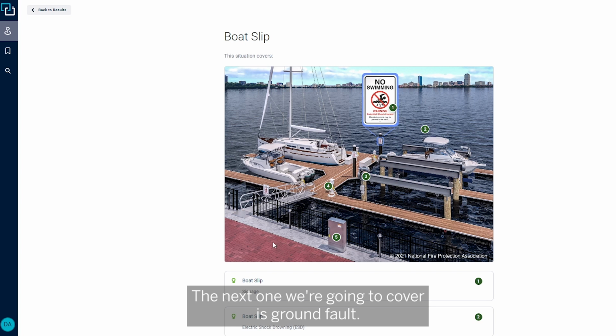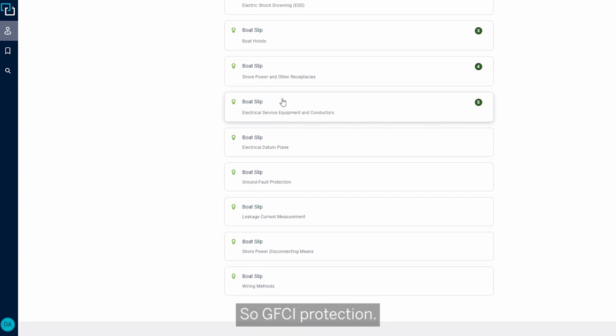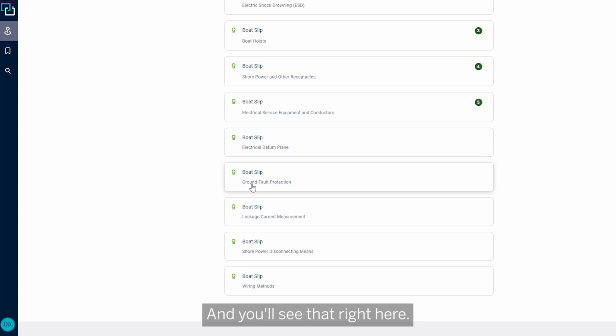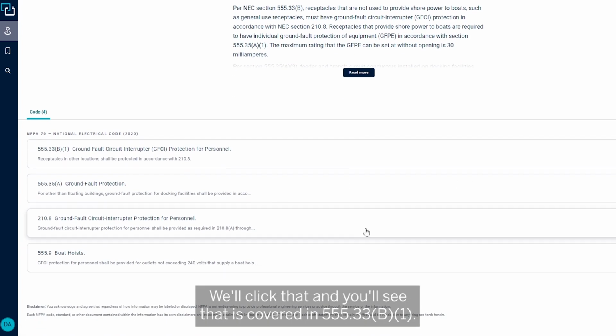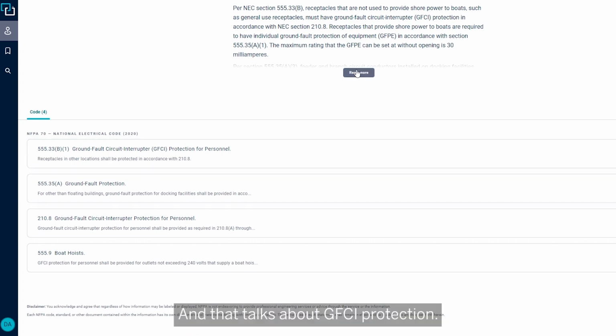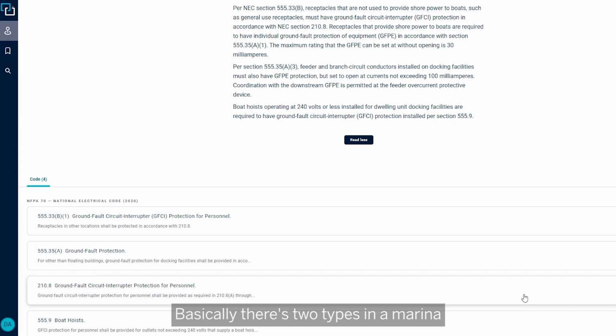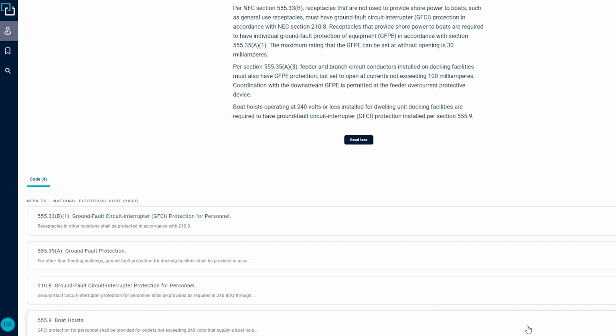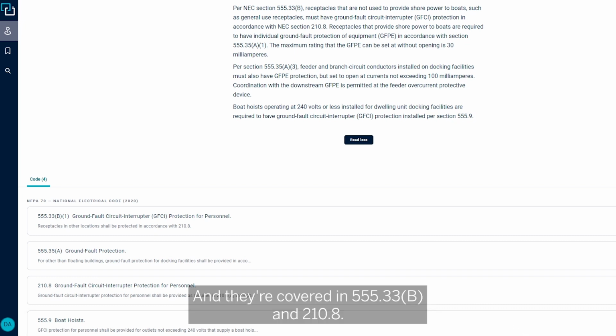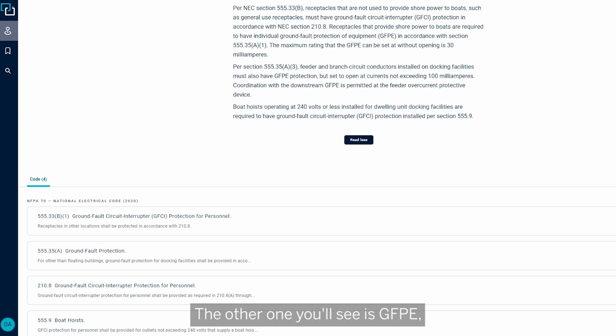The next one we're going to cover is ground fault, so GFCI protection, and you'll see that right here. We'll click that, and you'll see that it is covered in 555.33B1, and that talks about GFCI protection, which is basically, there are 2 types in a marina. You will see GFCIs, which are Class A, typically tripping at 5 milliamps, and they're covered in 555.33B and 210.8.